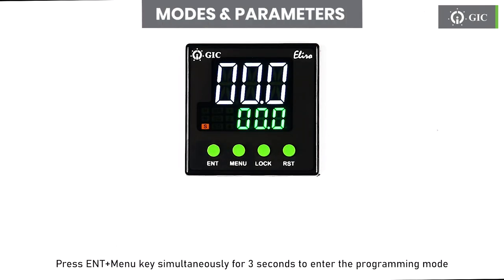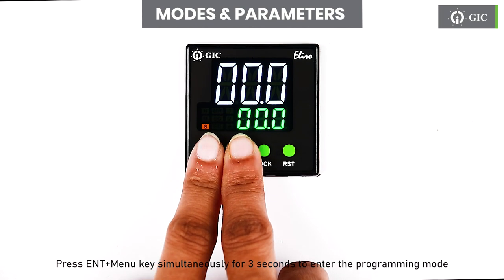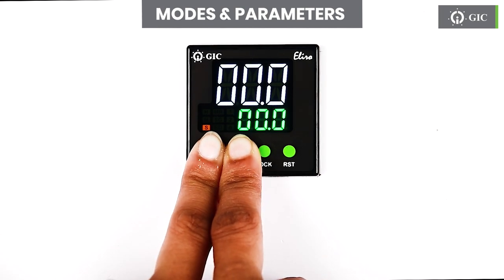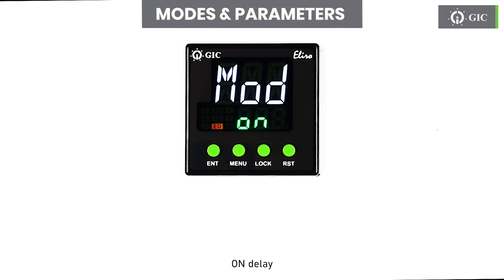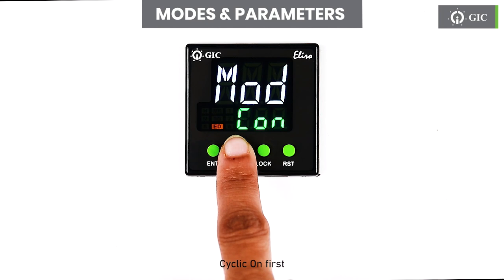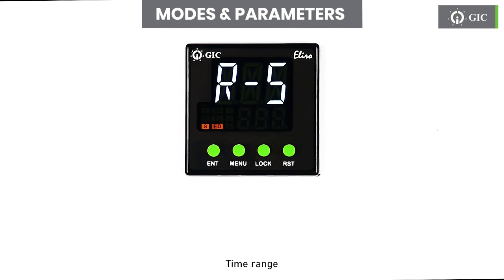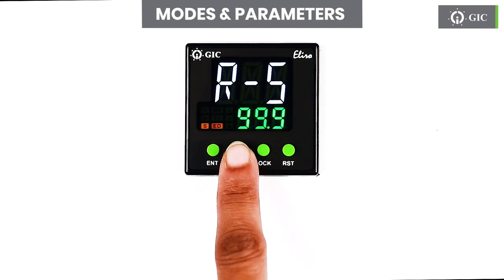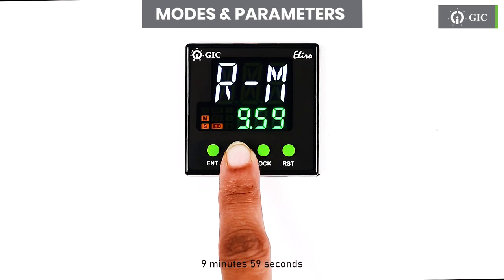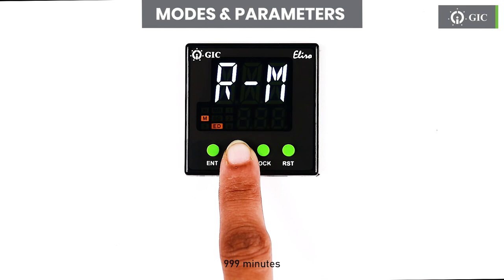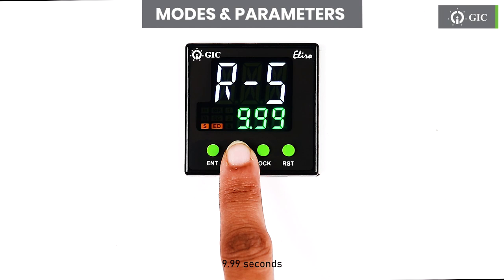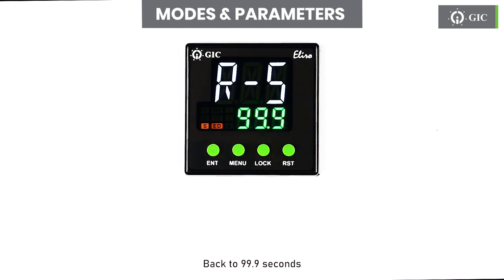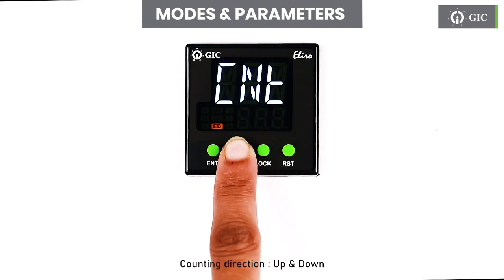Modes and parameters. Press Enter and menu key simultaneously for 3 seconds to enter the programming mode. There are 4 modes: on delay, interval, cyclic on first, cyclic off first. Time range, 99.9 seconds, 999 seconds, 9 minutes, 59 seconds, 99.9 minutes, 999 minutes, 9 hours, 59 minutes, 99.9 hours, 999 hours, 9.99 seconds. Back to 99.9 seconds, counting direction, up and down.